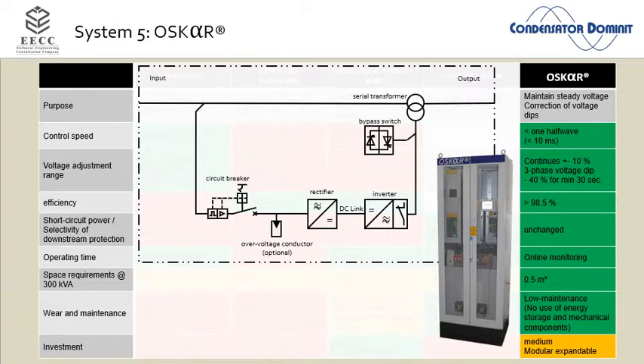The most important device on our whole active voltage conditioner is actually a reliable and fast bypass. That is your line of defense. That is human beings' safety. If somebody is putting his fingers in my switchgear for whatever stupid reason, but I saw it, even with experienced electrical guys, people make mistakes, then my fuse and my circuit breaker must trip as fast as possible. And that is something I do not want to prevent.